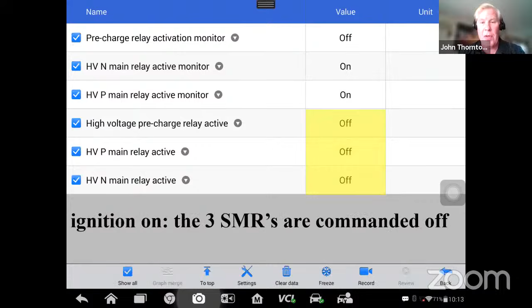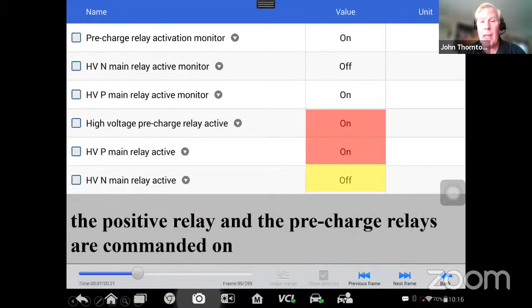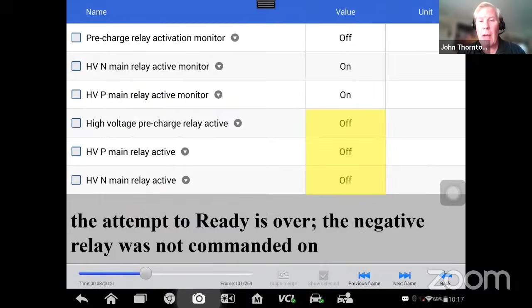And it's brief, that for that moment in time, both the positive relay and the pre-charge, which is on the negative side, were on for a short period of time. It was brief, it was brief. So my expectation is, if both of those are on - and think about where we're coming from - voltage should be made available to the inverter.